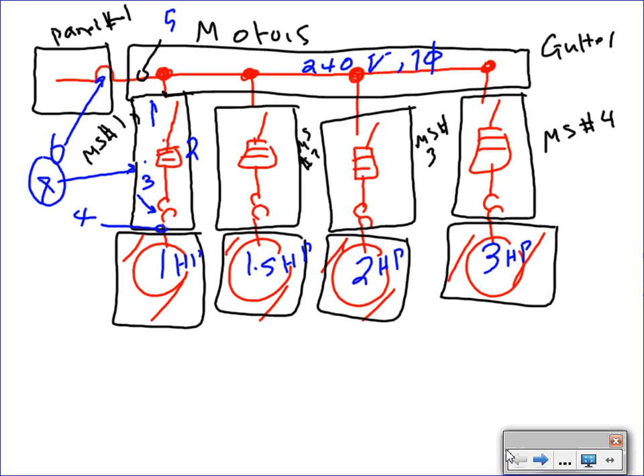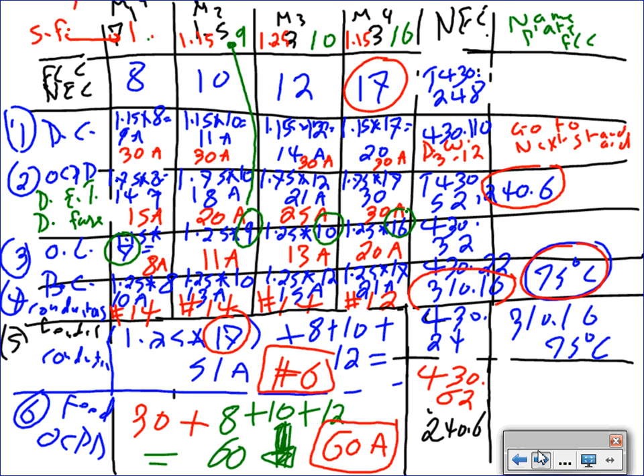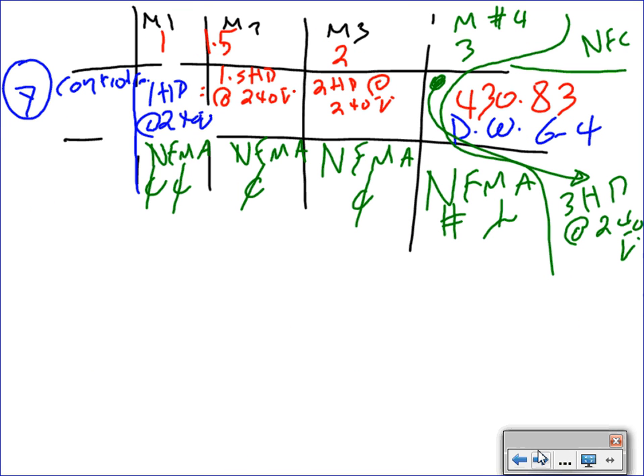I'm going to take another example, guys, but this time HVAC equipment. And instead of having 4, I want to have 2, because I don't want to do too much calculation, just 2. And for the HVAC equipment, I'm not interested in overload. The only things I'm going to be interested in are the disconnect, the overcurrent protection device, the cable, and the feeder. So I'm going to do something very similar for 2 loads of HVAC equipment, okay? And it shouldn't take that much because you guys are smarter than smart now.